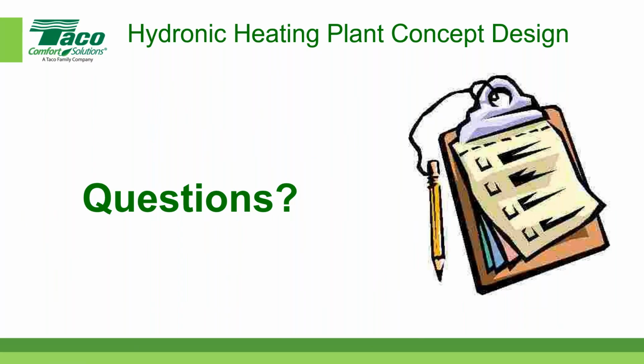And you go over these different options and parameters and make your recommendations. And sometimes, people will come back and say, well, I like your recommendation. The concept is valid, but you might want to consider the following modification. Maybe it's a critical facility and they can't have boilers at 33% each. In other words, if one boiler goes down, they still need 100% capacity. Usually it's things like hospitals that have those kinds of requirements. But you have a conversation to discuss the pros and cons, and maybe you have to go back and do some life cycle analysis in terms of first cost, operating cost, and potential return on your investment, or simple payback.